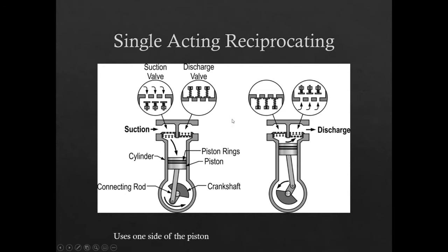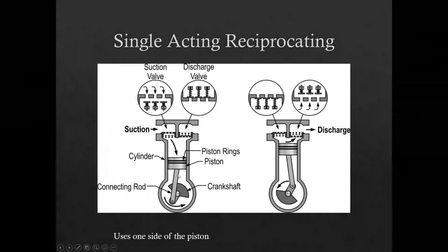This isn't any different than a gas engine, for example, which would operate on this exact same principle. As the piston works through its cycle and pulls down, the suction valves open, allowing air into the cylinder. Then as it makes its turn and starts coming back up again, the suction valves will close and the discharge valves will open as the pressure builds with the stroke compressing the gas on its upward stroke. And that's really basically how it works.